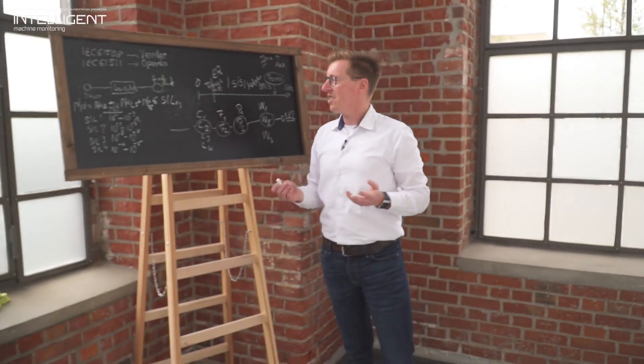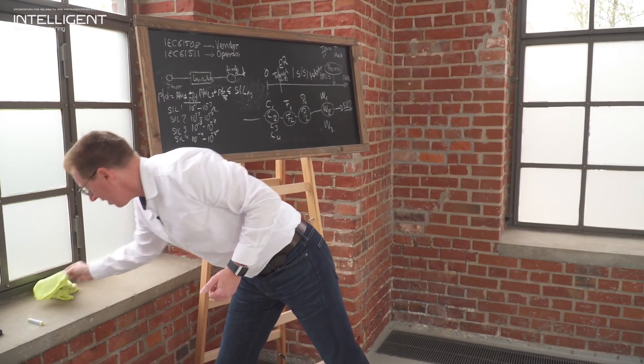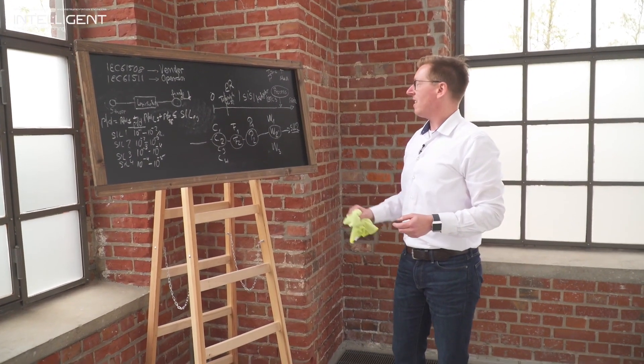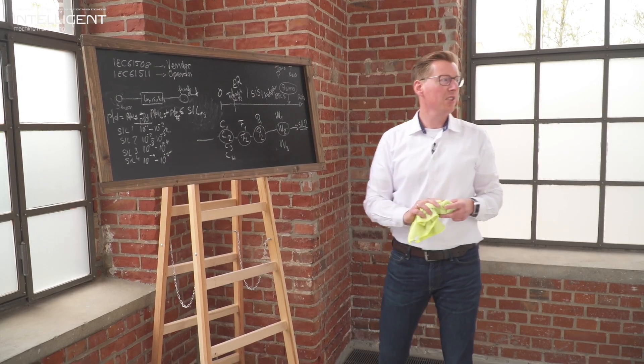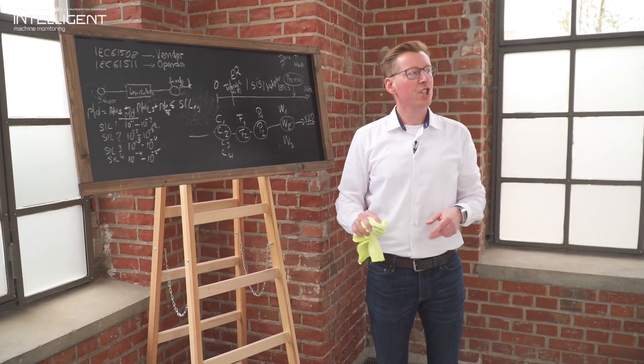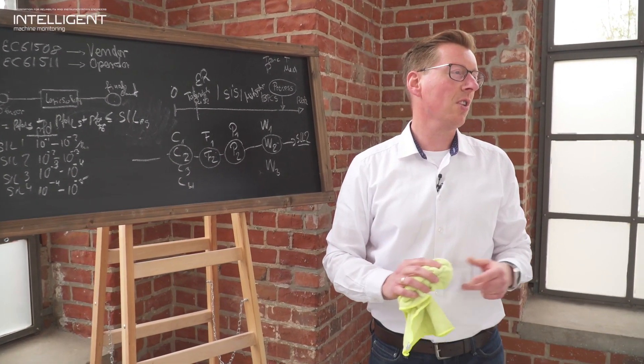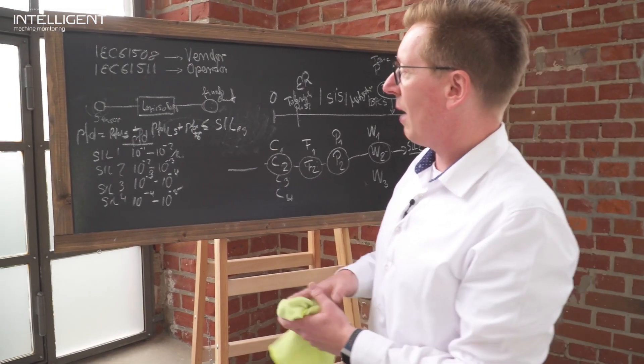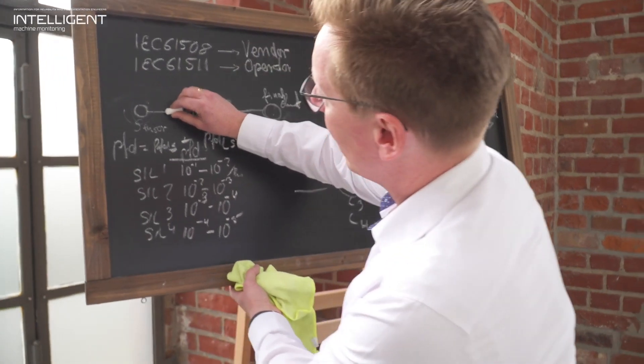Okay, so there is no way for the operator to make it a little bit less critical. Because I think with each SIL level you are adding to your system, I expect that there might be some money attached to it. So more investment, the higher the SIL level. This in a sense is true, but there is another aspect to that. Say you have a solution in mind and your requirement may be for a SIL 2 system. You can do little tunes and twists to your existing systems, so you achieve a higher SIL rating of the system of choice, or also improve the PFD, for example, by implementing some redundancy in your systems.